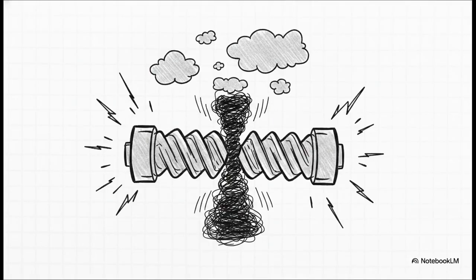First up, the screw compressor. Imagine interlocking male and female rotors, literally giant screws, rotating together to trap and just relentlessly squeeze the gas into a smaller and smaller space. It's incredibly durable because of its simple structure, but the real superpower here is precision. Using a slide valve or an inverter, it perfectly adapts its capacity anywhere from 10 to 100%. It's the ultimate workhorse for constantly fluctuating server loads. The catch? When those giant metal screws are spinning at top speed, they definitely generate some serious noise and vibration.